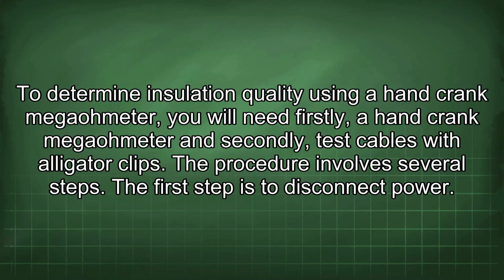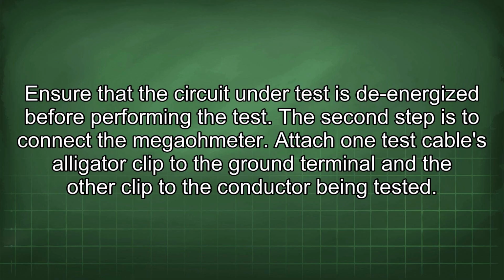To determine insulation quality using a hand crank megaohmeter, you will need, firstly, a hand crank megaohmeter and, secondly, test cables with alligator clips. The procedure involves several steps. The first step is to disconnect power. Ensure that the circuit under test is de-energized before performing the test.